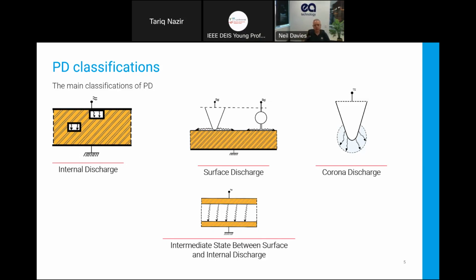The next, and what is possibly the most common type of discharge where you're looking at air insulated switchgear in particular, is discharge that's happening across the surface of insulation. So as soon as we moved away from porcelain insulation towards more polymeric insulations in the 1970s and 80s, and going away from compound insulated cable boxes to dry terminations, we started seeing an upsurge in surface discharge activity and problems occurring that way. So this is where you're getting the discharge breaking down across the surface of insulation. That can also be phase to phase if you've got inadequate spacing, say in cable terminations.